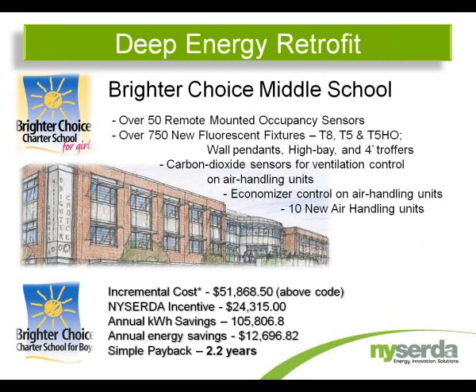Moving into a deeper energy retrofit was the Brighter Choice Middle School in Albany, New York. We provided over 50 remote-mounted occupancy sensors, over 750 new fluorescent fixtures—T8s, T5s, T5 high output, wall pendants, high bay, and 4-foot troffers. We also installed demand-controlled ventilation, and economizers were added to the new air handling units.